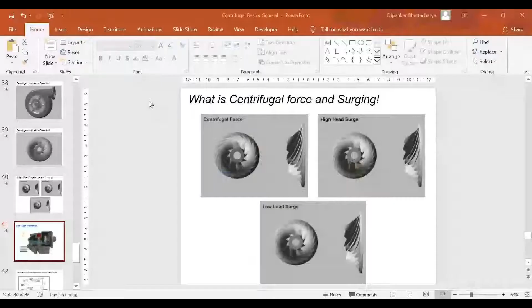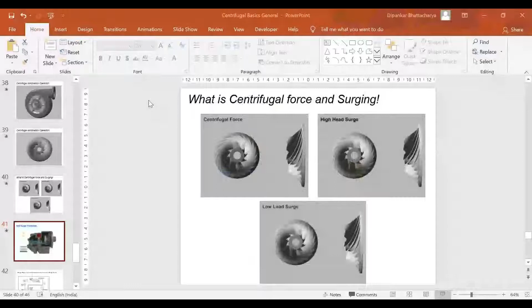So here I would like to talk about one particular specific component which is very popular in our industry, and different people have different opinions about that. But what we need to understand is that it is more of a protection device for your centrifugal compressor, which is an expensive one, and you need to provide that to ensure that under no circumstances the machine gets into a stall mode or a surge mode, because that can actually damage your compressor permanently. That particular component is called hot gas bypass. We have different terminologies existing in the market. Some call it hot gas bypass, some call it envelope stability control, some call it anti-surge device.